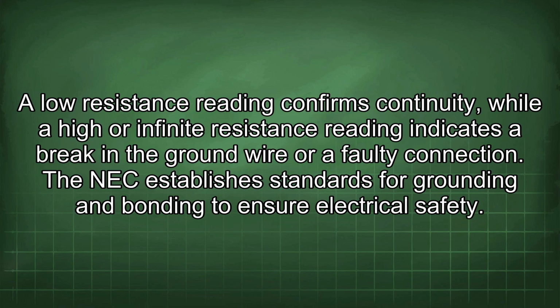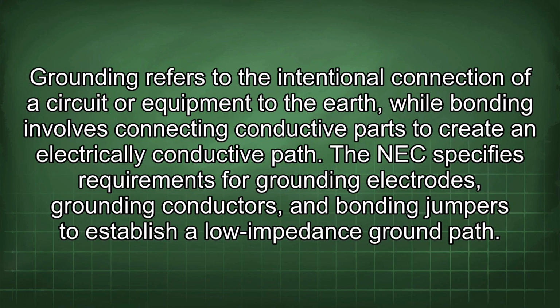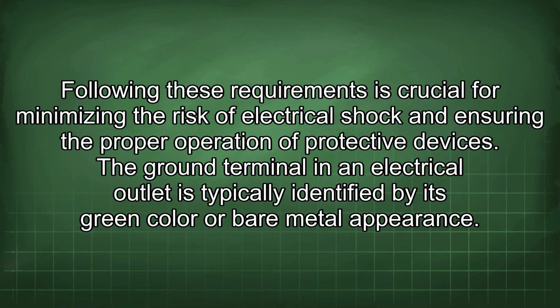The NEC establishes standards for grounding and bonding to ensure electrical safety. Grounding refers to the intentional connection of a circuit or equipment to the earth, while bonding involves connecting conductive parts to create an electrically conductive path. The NEC specifies requirements for grounding electrodes, grounding conductors, and bonding jumpers to establish a low-impedance ground path. Following these requirements is crucial for minimizing the risk of electrical shock and ensuring the proper operation of protective devices.